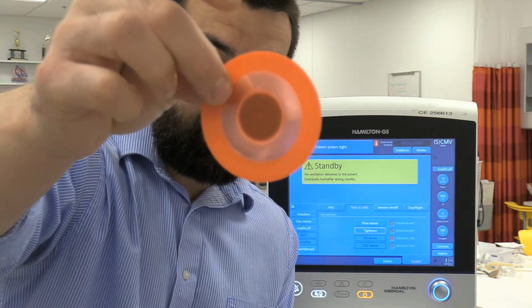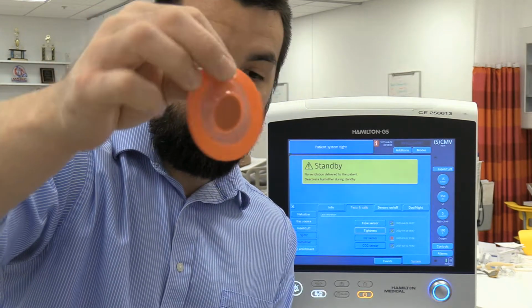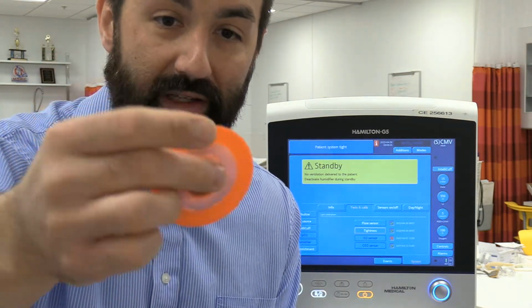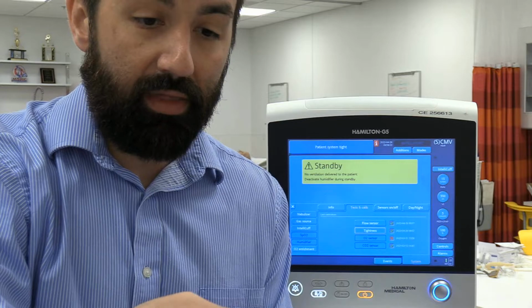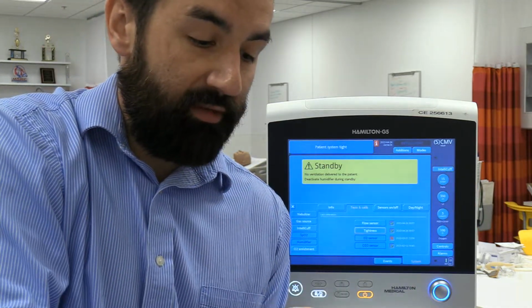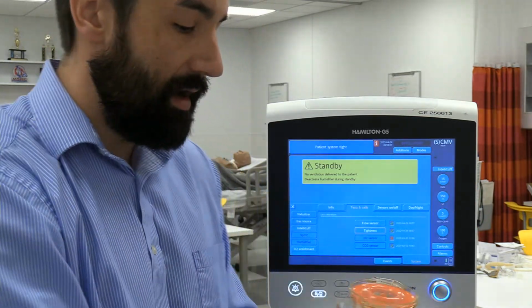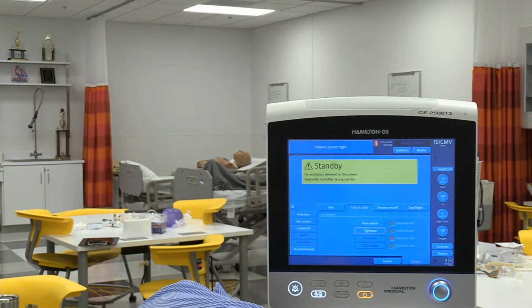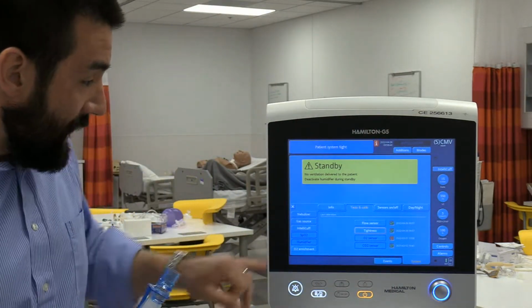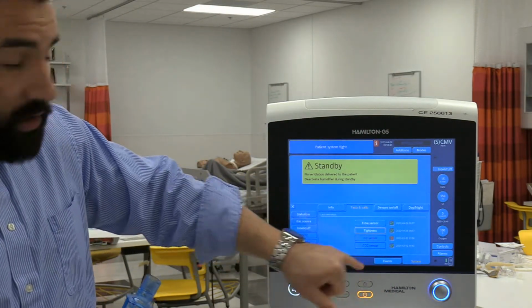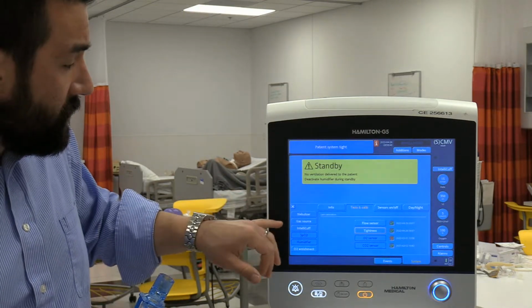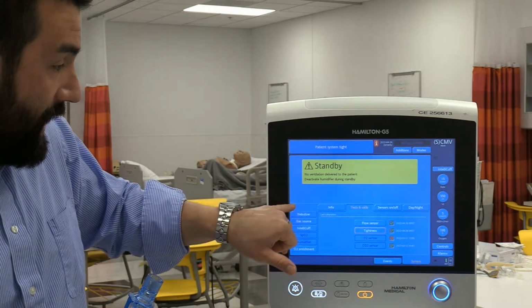I don't know if you can see clear enough. No, not going to be able to, but it's actually labeled and tells you what side to put down. Ultimately, the weight side there is always going to be facing up, and the pin's going to be kind of resting on right there. When you put this in, it just kind of seats on a little metal flange, and it kind of turns and locks in place. Okay, so we're tight here, we're good, we got all green lights. The O2 sensor I would do as well. You can calibrate the O2 sensor when it's on a patient, but it should be done ahead of time.